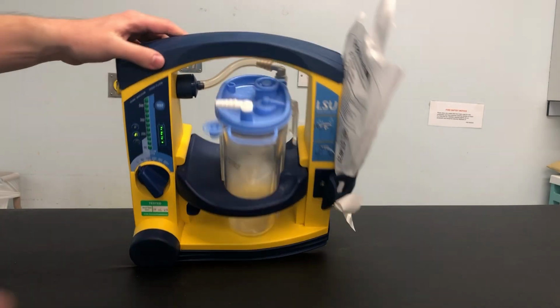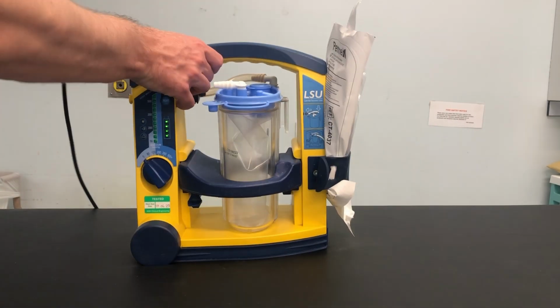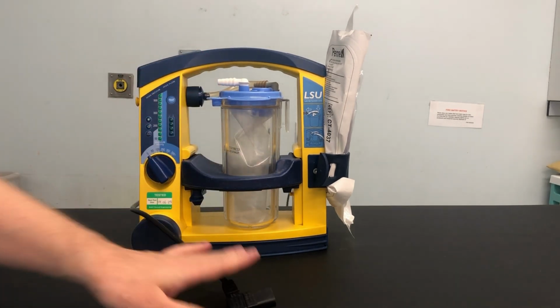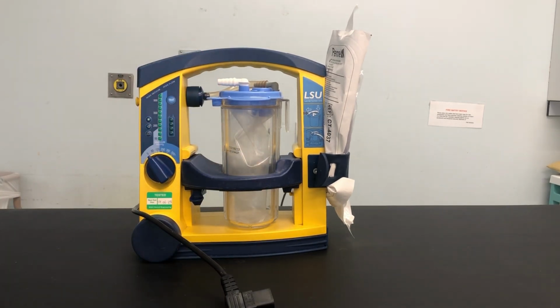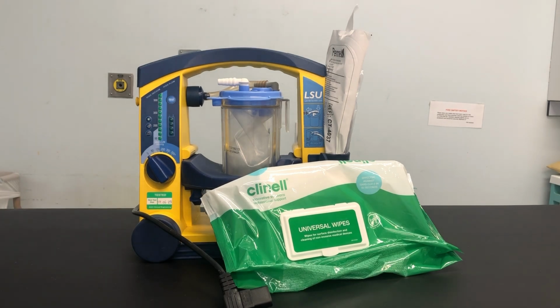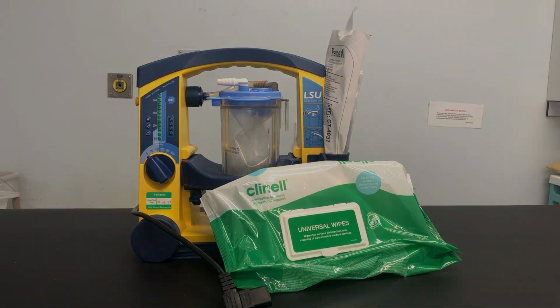For cleaning, disconnect the LSU from external power prior to cleaning to reduce the risk of electrical shock hazard. Do not immerse the LSU or allow it to stand in water or other liquid, as this can damage the device and cause an electrical hazard. Do not pump any cleaning solution or other liquids through the vacuum pump, i.e. through the vacuum connector, as this can damage the LSU. Inspect all parts of the LSU for damage and excessive wear. Use a Clinell red after use and green on a regular basis to clean external surfaces.